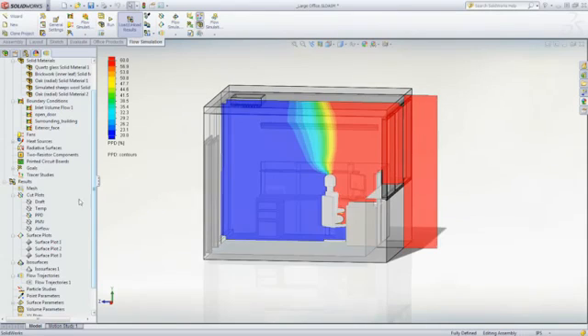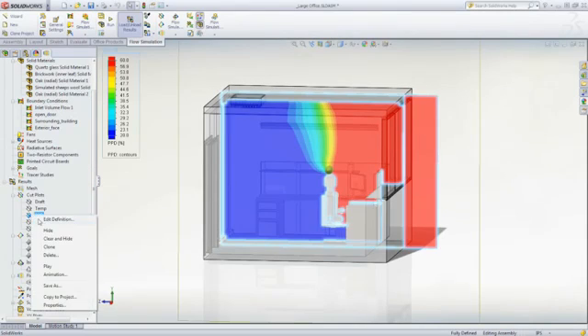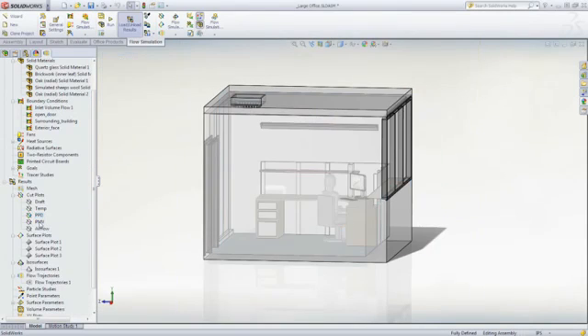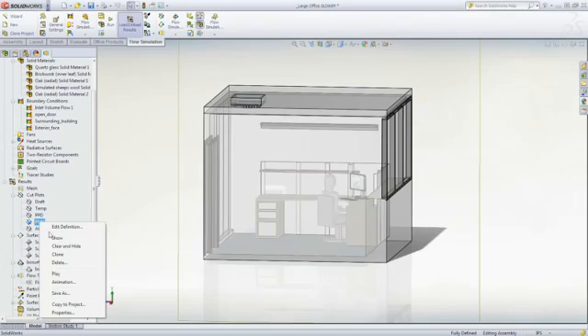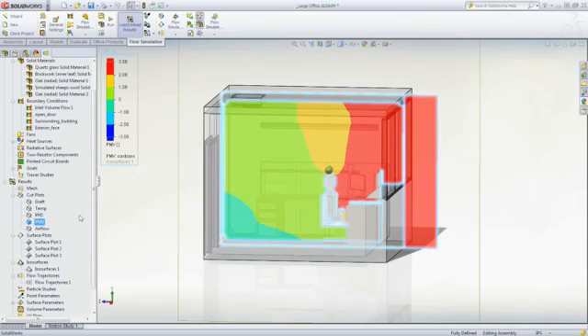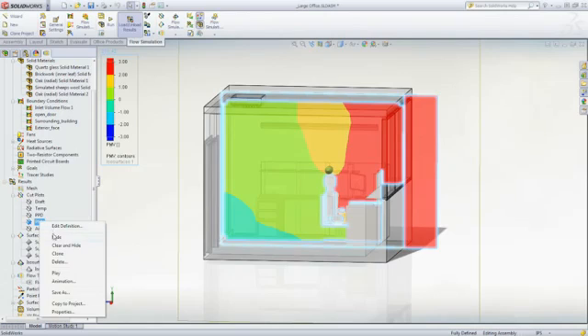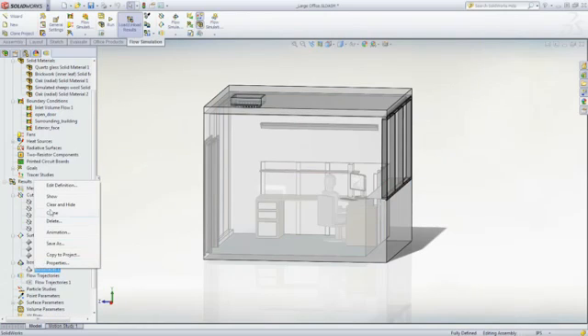PMV is the predicted mean vote where the goal is to be as close to zero as possible. A value of plus three indicates that it's too hot, and a value of minus three indicates that it's too cold.